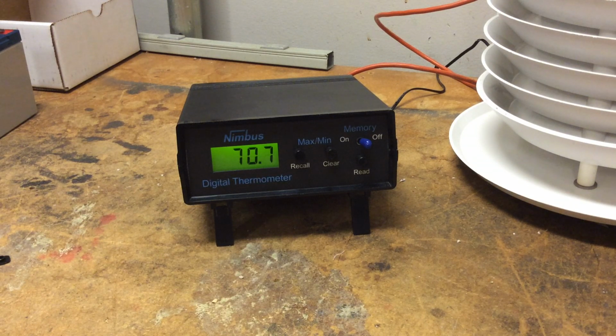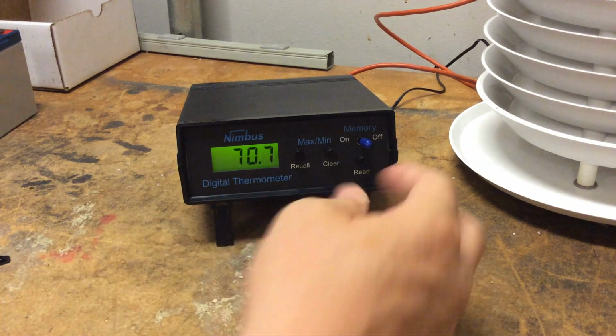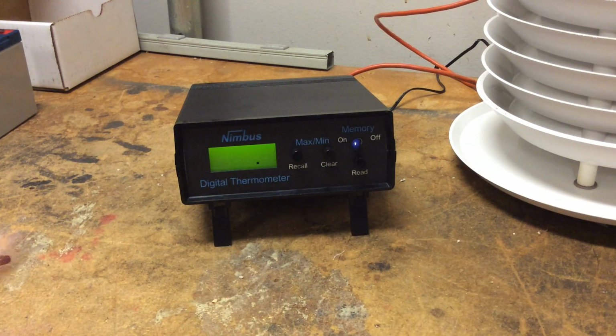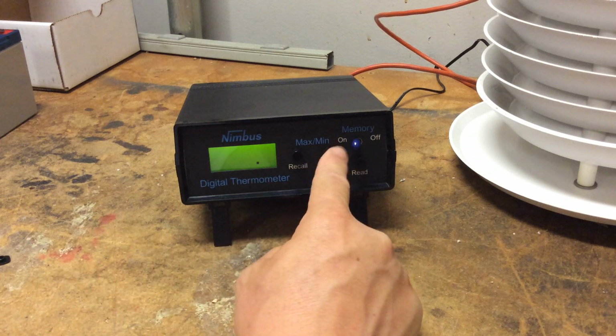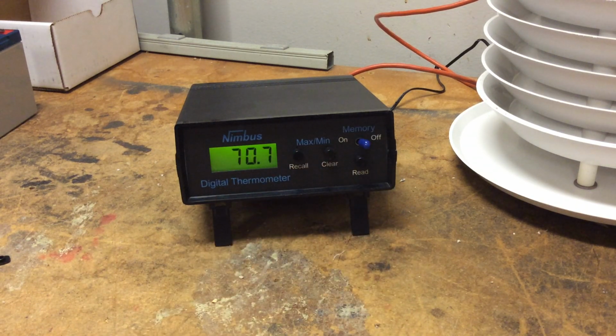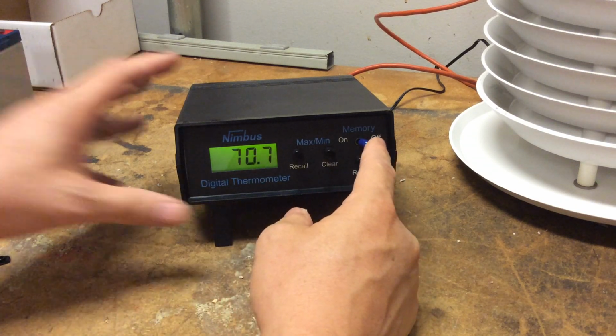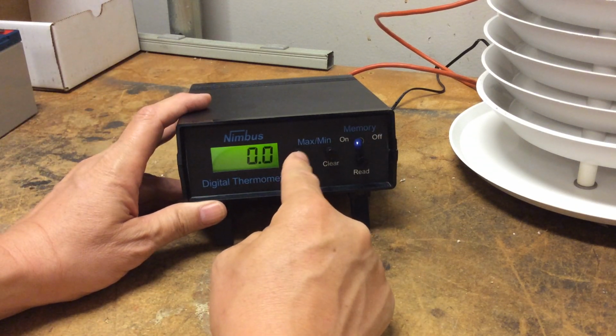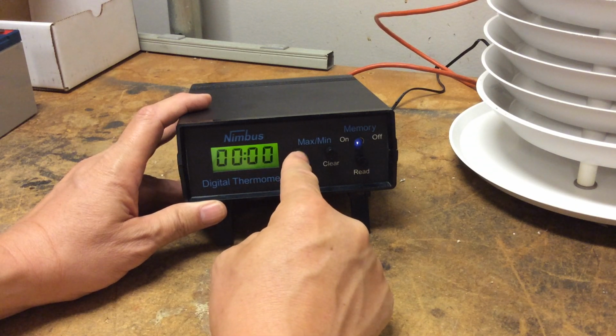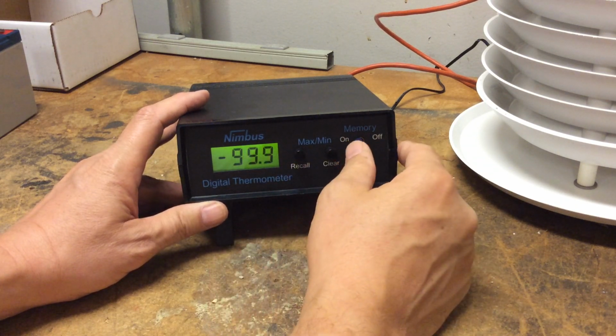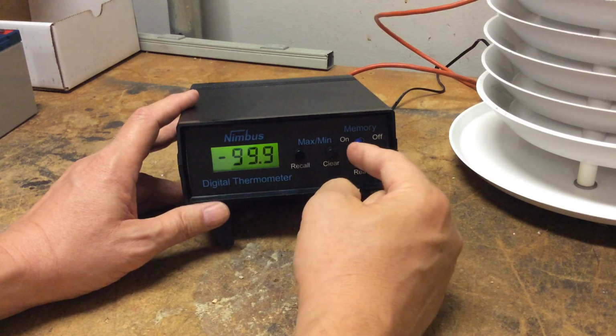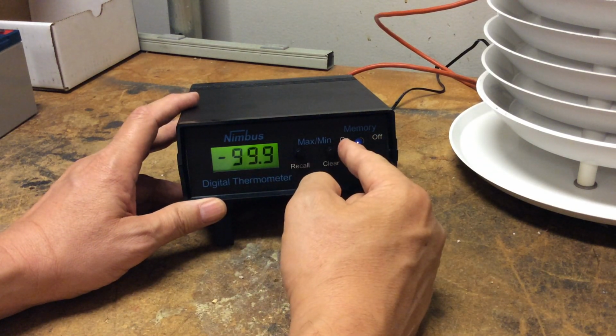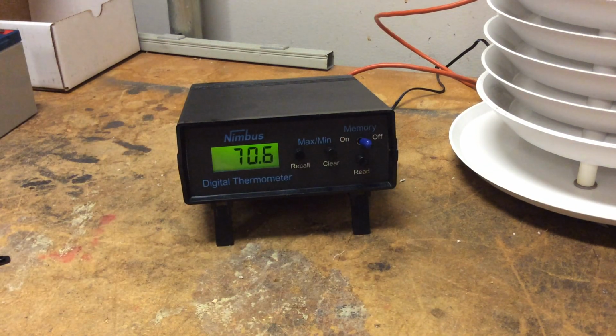Some other troubleshooting things you look at is, let's say the display is blank. You see the display is like that. Some of the things you want to check for is to make sure the memory switch is not in the on position, which it is. So switch that back off, and you should see something on there. If the display reads numbers much too small, the instrument might have been left on. Let's say we were in the recall mode, and you had a low temperature on there, and you happened to leave that on in the memory function. Always make sure that memory function, once you're done using it, is turned back off.